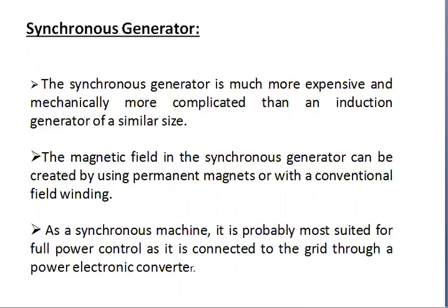The converter has two primary goals. The first one is to act as an energy buffer for the power fluctuations caused by the inherently gusting wind and for the transients coming from the net side. The second one is to control the magnetization and to avoid problems by remaining synchronous with the grid and controlling the frequency. So applying such a generator allows variable speed operation of the wind turbines.